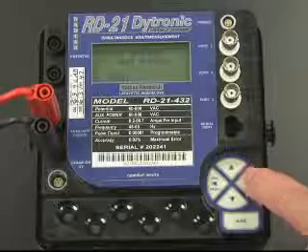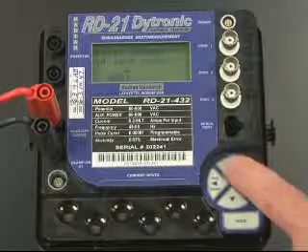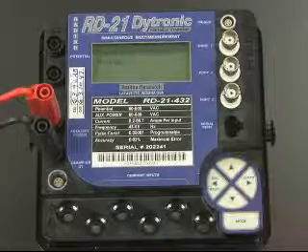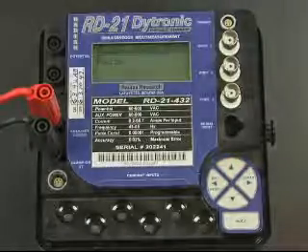Once the correct number of revolutions have been accounted for, the test results will be displayed. The total amount of energy will be displayed, along with the meter's percent registration and percent error.